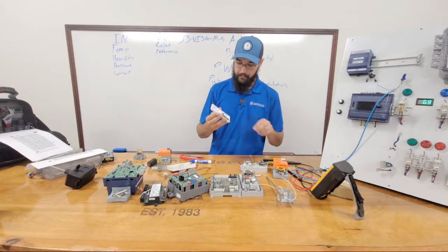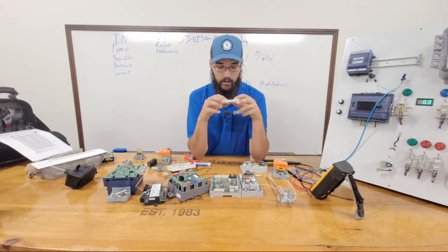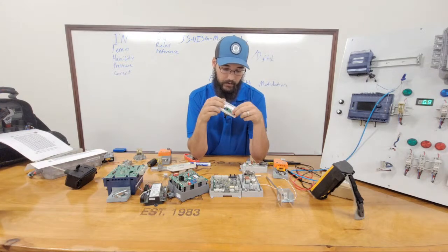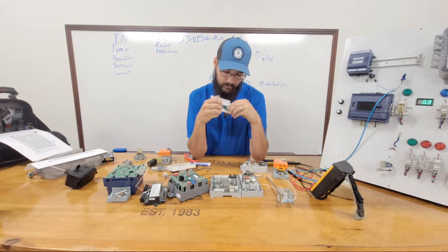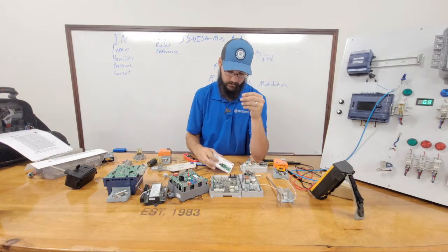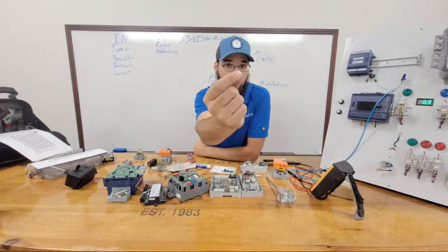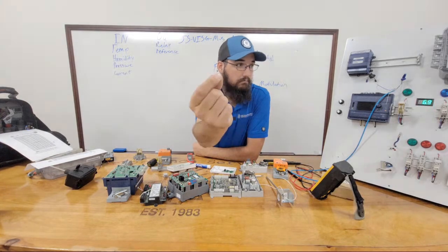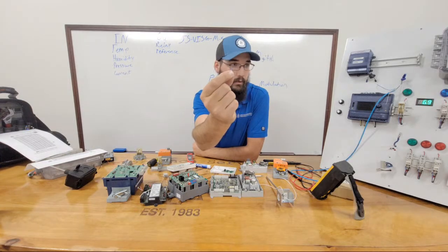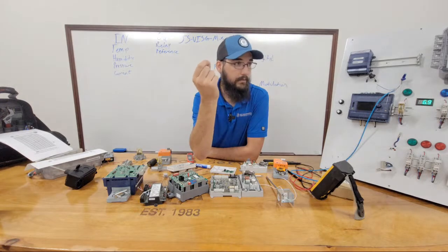Anyway, as a technician, you're trying to troubleshoot this, these Honeywells are actually removable. So we can pluck this little guy out. And let's just say this tiny little booger goes bad. Ultimately, pull it out, get a new one, stick it in, and you're probably fixed.